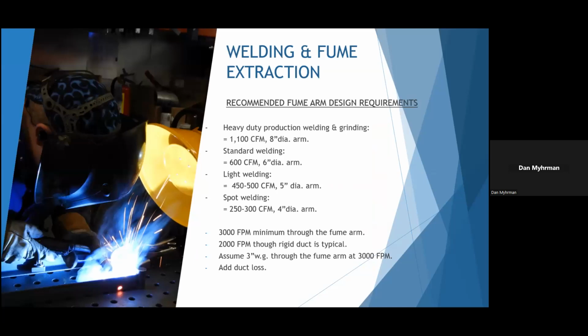Design parameters for welding and grinding. You want a minimum of 3,000 feet per minute through the fume arm. That is key. Any less than that, and basically the arm has to be a lot closer to the welding process, which can essentially interrupt the arc. You may even start sucking some gases through the system as well.